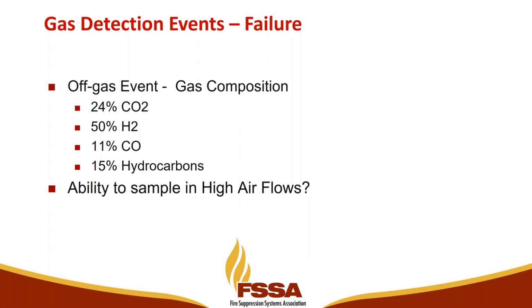So what do we see when we get into an off-gas event? There's a variety of components, and keep in mind this is a generic summary, because any one of these percentages can be up or down depending upon the composition of the battery, the type of battery, the energy levels, etc. So these are just relative numbers to give you an idea. So in an off-gas event, we see about 50% hydrogen, about 15% hydrocarbons. And that little puff may also have to be picked up in a high airflow event, because you're moving a lot of air through these containers.